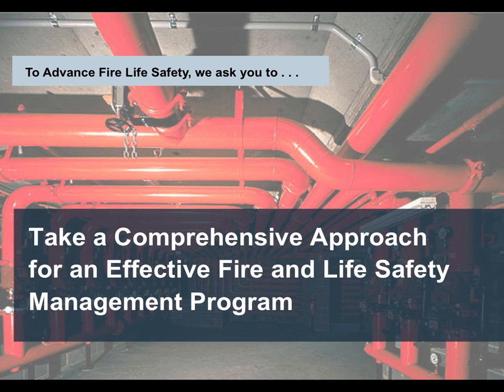So that was a quick run through on NFPA 4. I hope it wasn't too fast for many of you, but you'll get copies of this presentation, and I think it's a good reference. NFPA 4 today is just starting to be included in the model National Building and Fire Codes. What does that mean? That means that in the 2018 edition of the International Building Code, the International Fire Code, and NFPA 101 is where you'll start to see requirements for NFPA 4 execution. So it's not here at this moment today unless a specifying engineer or a local AHJ or something of that nature activates this and puts it forward.